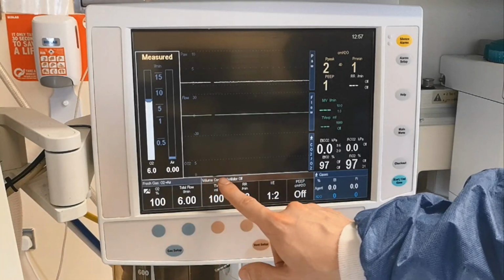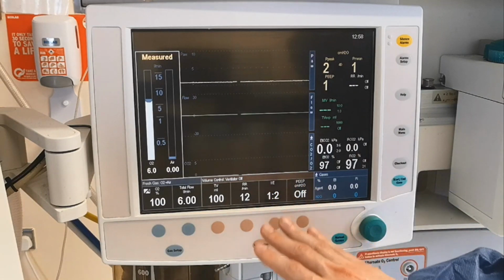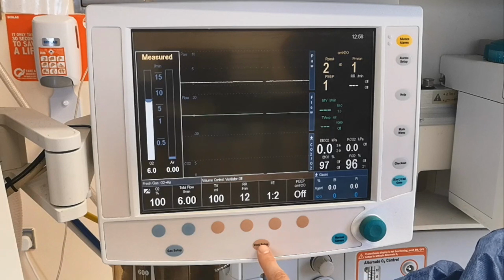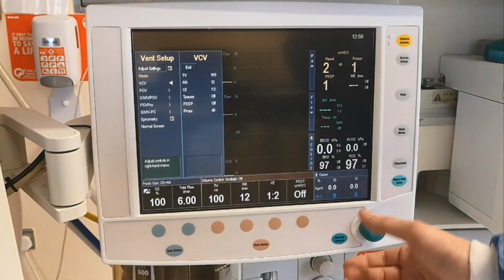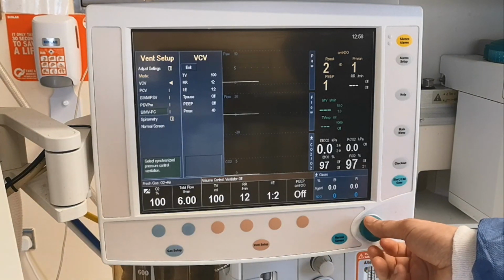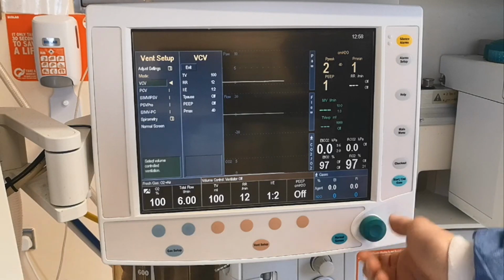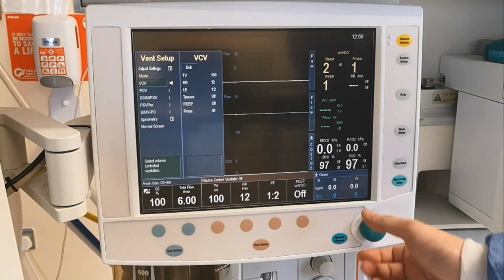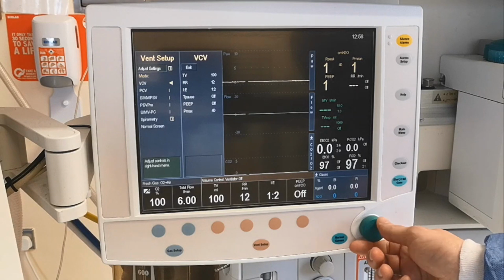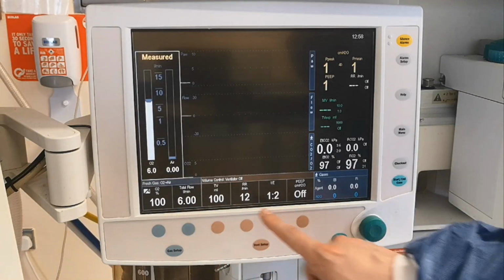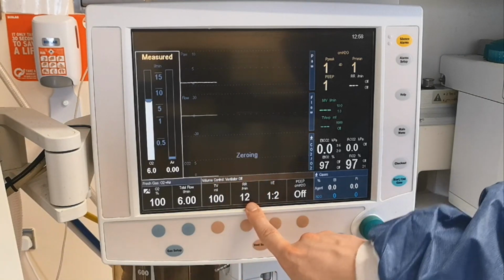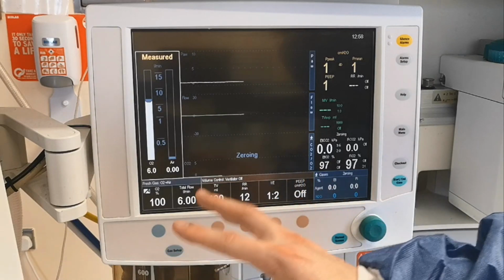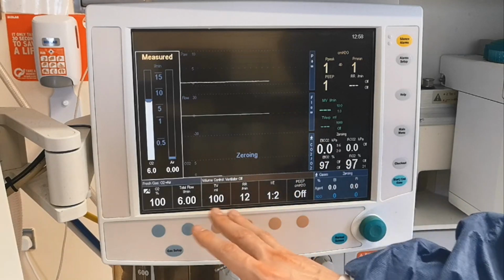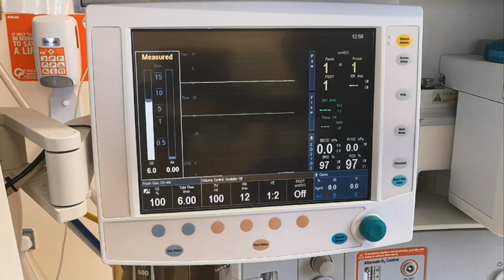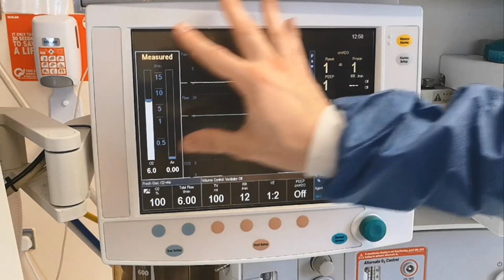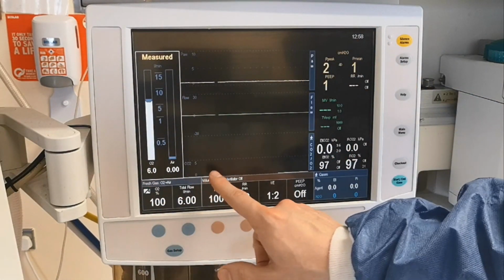Now here we're talking about volume control mode, okay? Obviously you have several ventilation modalities here. You can choose them by selecting ventilator setup, and then here you have several modes. You have volume control, pressure control, and others. For the sake of simplicity, we'll just go with volume control mode. That's what we want to do. Volume control means that you control the volume that you give, the rate, the ratio, and the PEEP, but you do not control the pressures generated in the patient's airways, because the pressures depend on the volume and on the patient's compliance. So for simplicity, we're always going to use volume control mode.